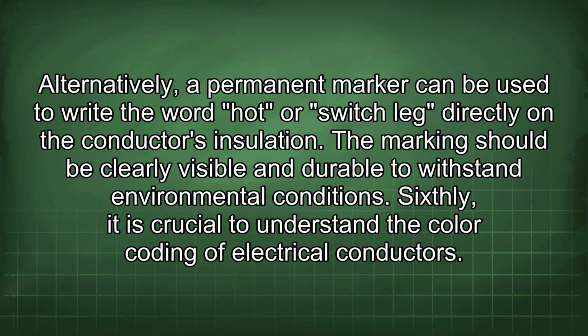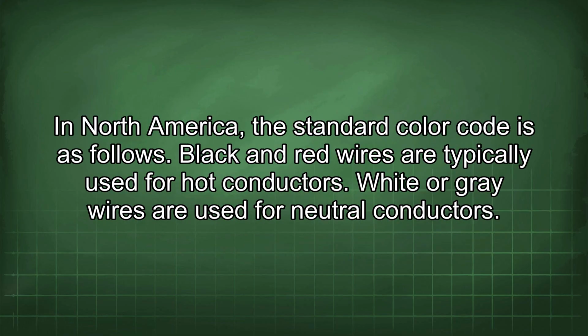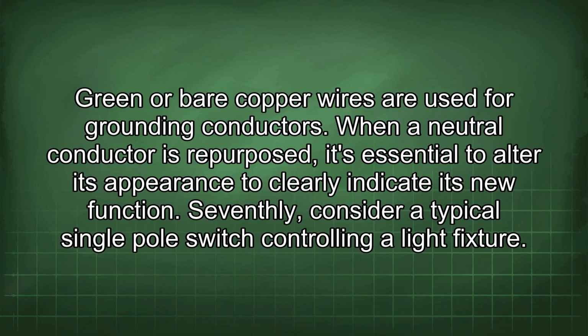Sixthly, it is crucial to understand the color coding of electrical conductors. In North America, the standard color code is as follows. Black and red wires are typically used for hot conductors. White or gray wires are used for neutral conductors. Green or bare copper wires are used for grounding conductors. When a neutral conductor is repurposed, it's essential to alter its appearance to clearly indicate its new function.